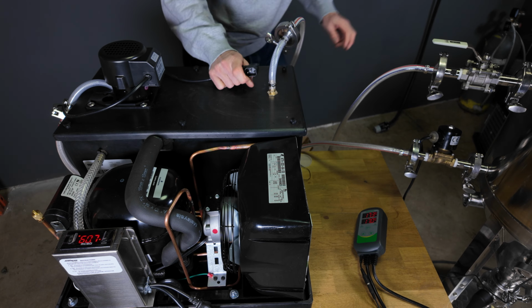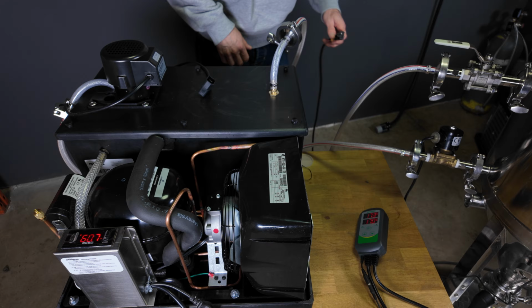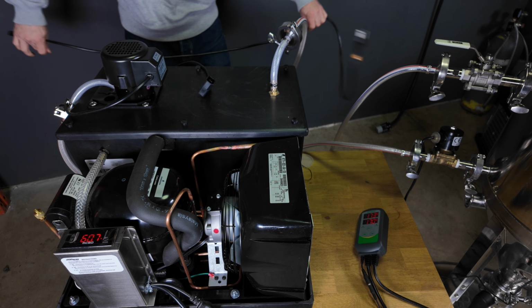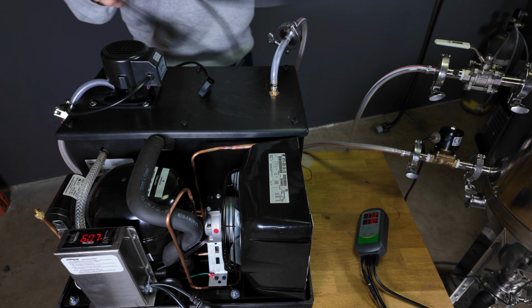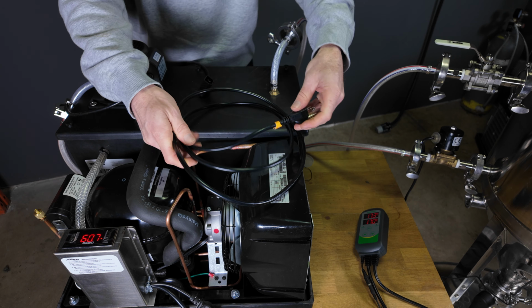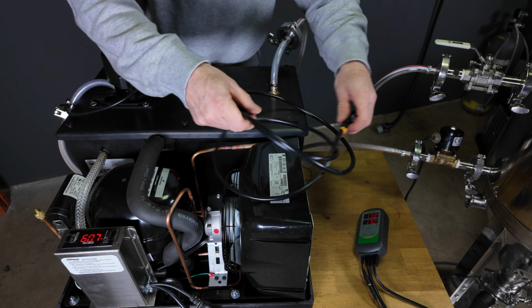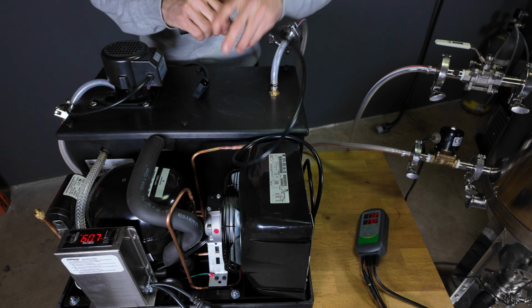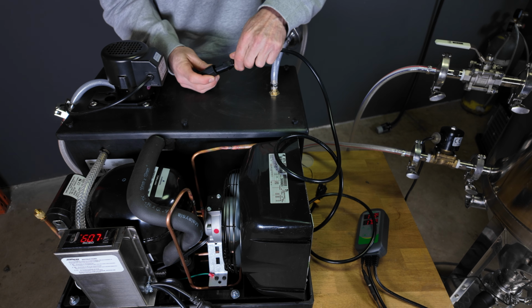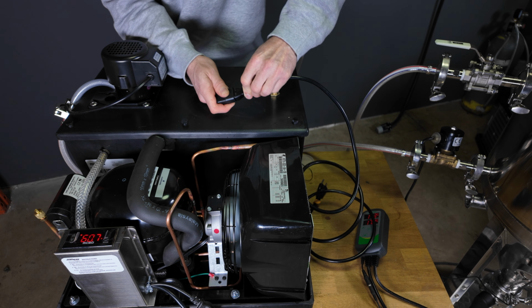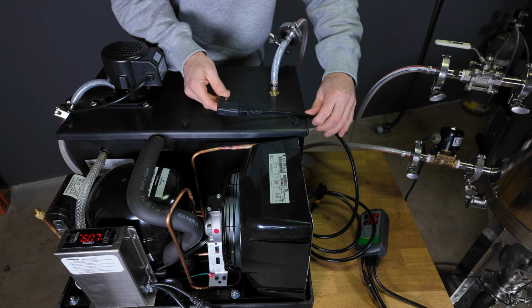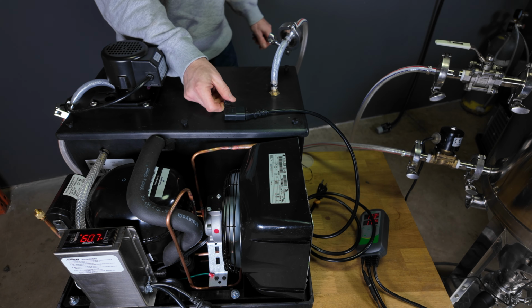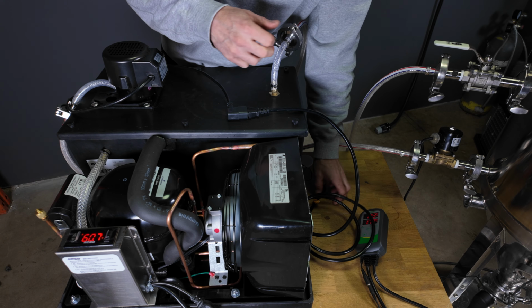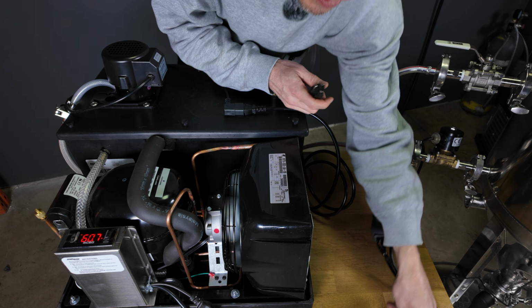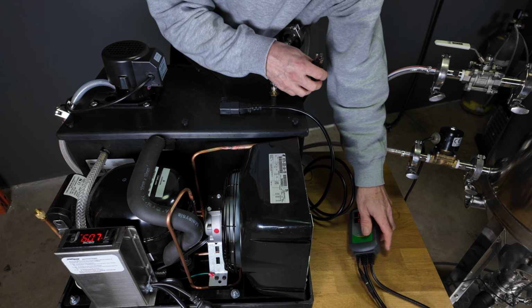But with this setup, we include a separate power cord so you can run the pump through the external temperature controller instead. In this configuration, the chiller maintains the Glycol at its preset temperature, and the external controller activates the pump only when there's a call for cooling. So Glycol is circulated through the jacket as needed, then stops once the set point is reached. This gives you much more precise control at the fermenter rather than relying on the chiller's internal controller.